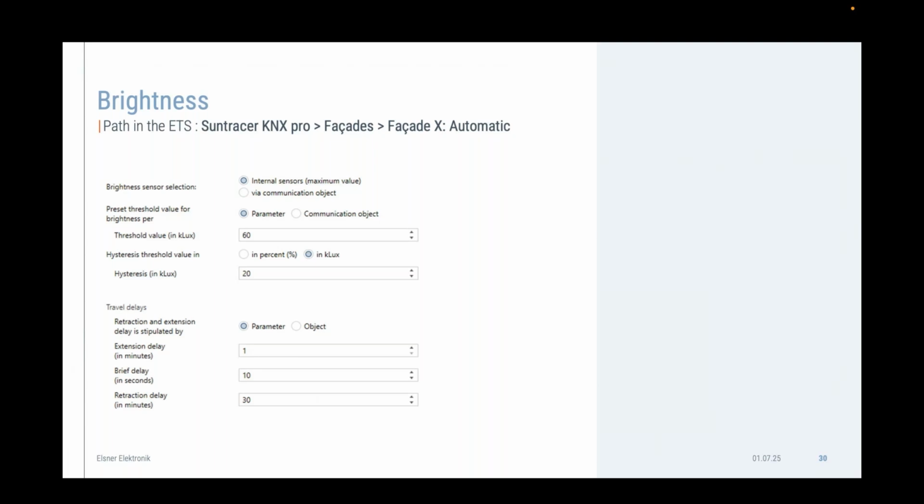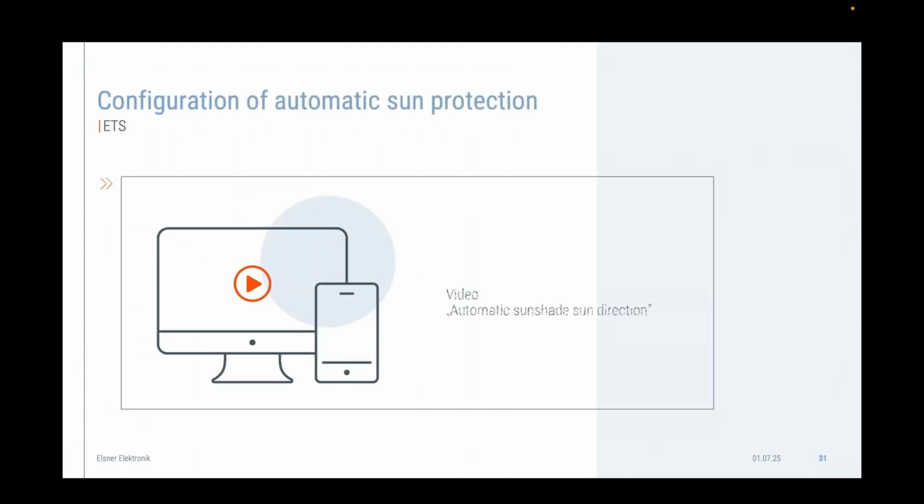A very easy example: if the brightness limit value of 60 kilolux is exceeded for 1 minute, then the shade is extended. If there is a short cloud after this extension, so there is a short drop below the 60 kilolux, let's say for about 10 seconds, then the slats can be opened a little bit to let enough daylight into the room, in order to limit the artificial lighting and have a comfortable brightness in the room itself. But if the value falls below the limit for 30 minutes, then the shading retracts again. Why do we do this? We do this to have a very calm picture of the facade. We don't want to overheat the engines that are moving our blinds, and therefore we use the retraction delays in all those thresholds. More about that in the next video.